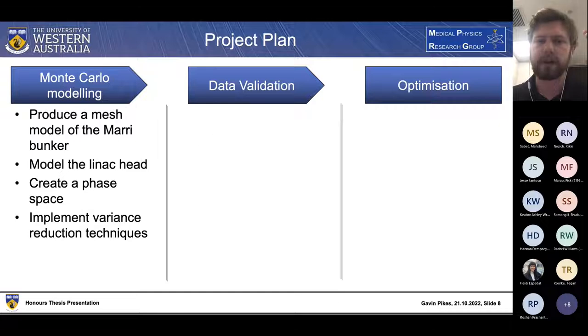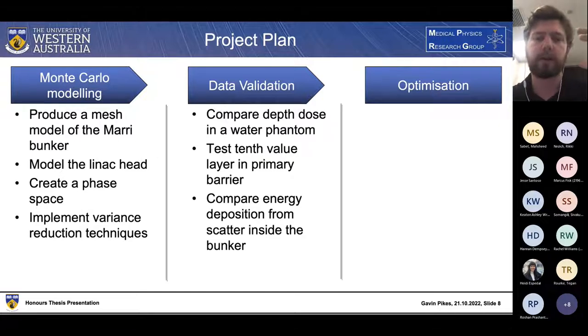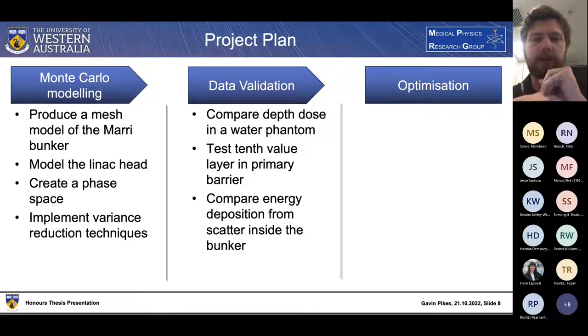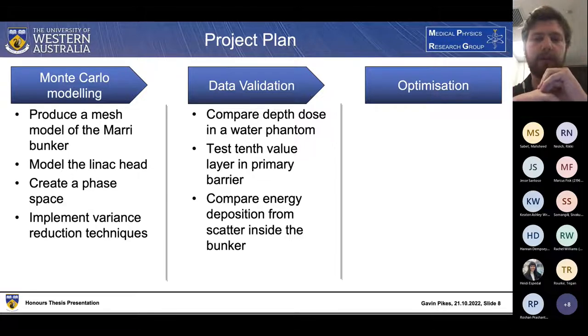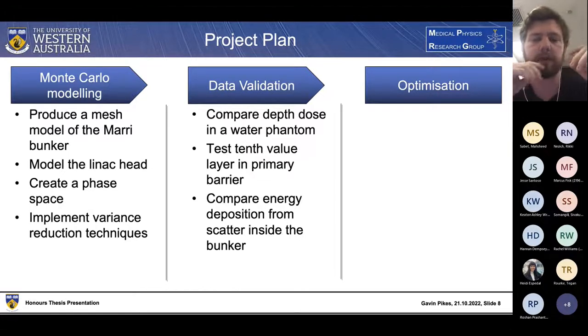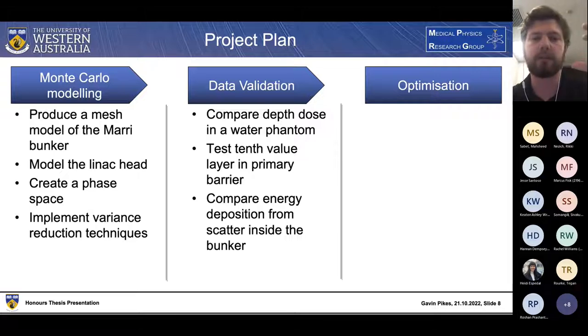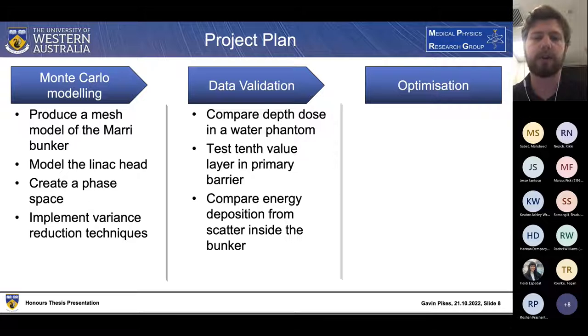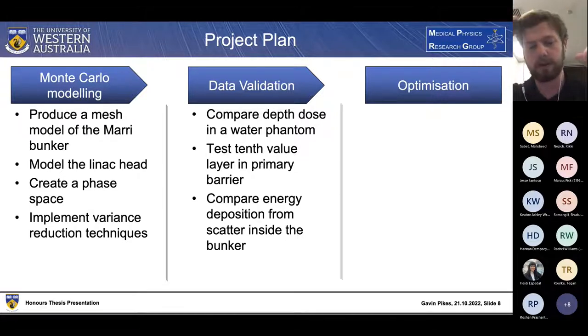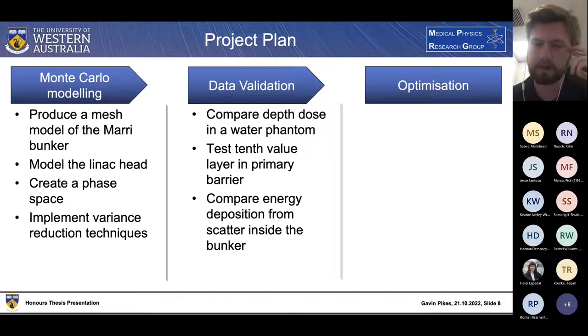Moving into the data validation section, we're looking at three main areas: comparing the depth dose curve within the water phantom between simulated and measured results; looking at the tenth value layer within the primary barrier comparing documented and simulated values; and a comparison of energy deposition within the scatter from measured and simulated values.